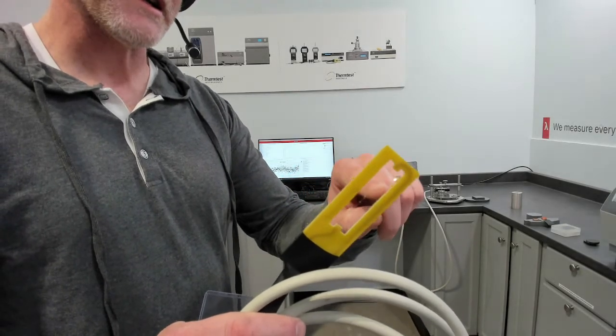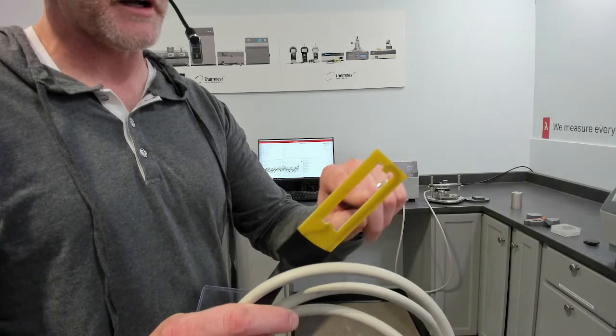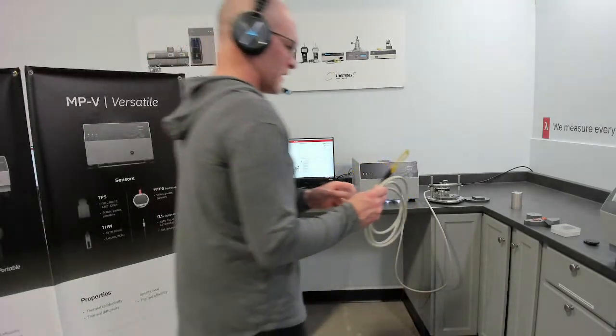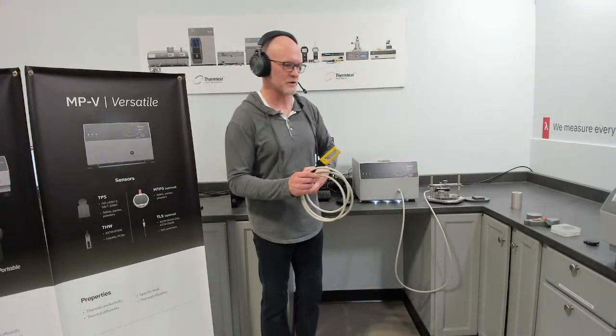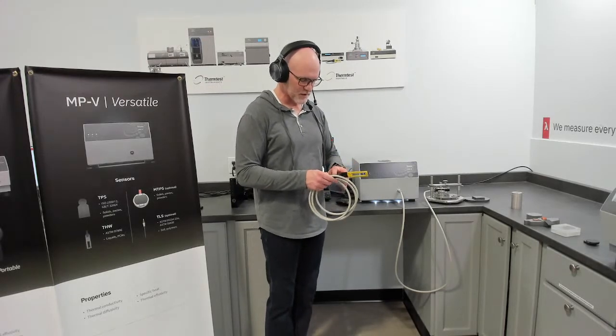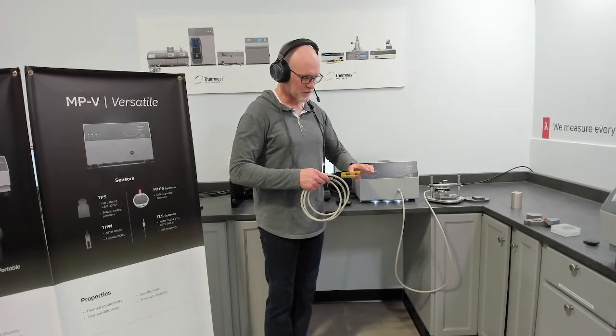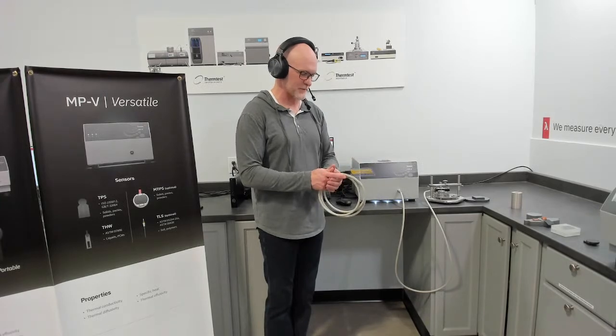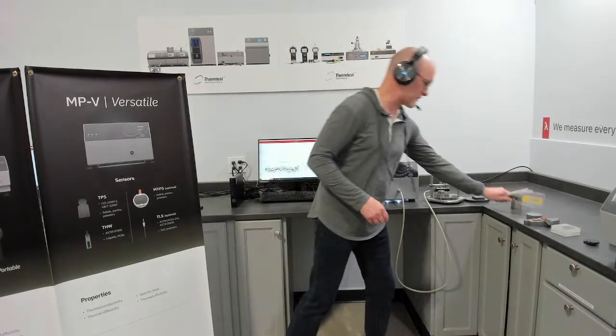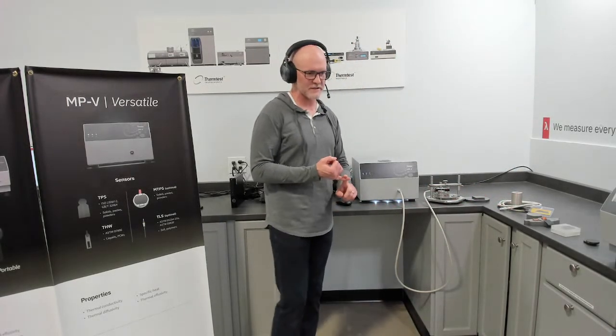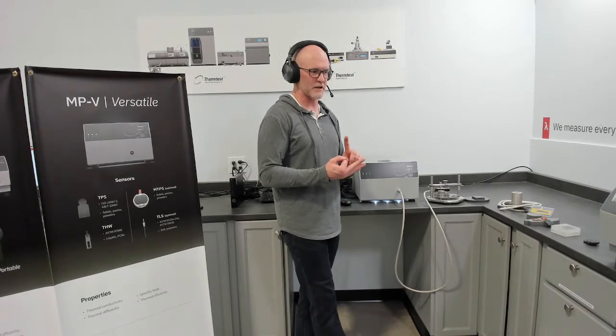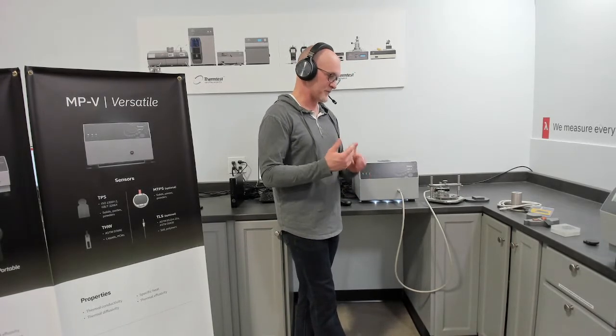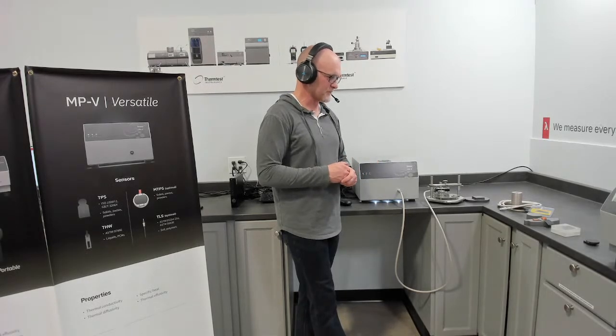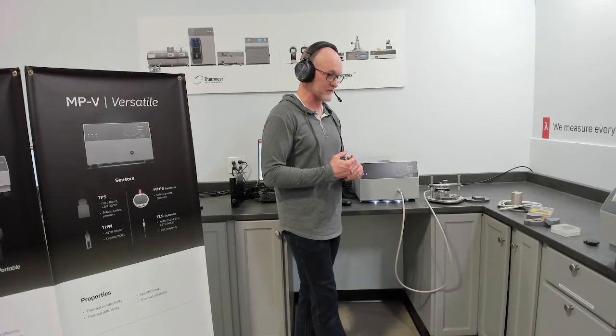Why don't you get convective effects? You have a small area of that wire, short test times, and low powers. So we still achieve optimum temperature rise, but through selection of those parameters we ensure we're not getting convection effects. And that allows us to measure thermal conductivity, thermal diffusivity, and volumetric specific heat. And if you input density, you get specific heat for liquids and phase change materials according to ASTM D7896.